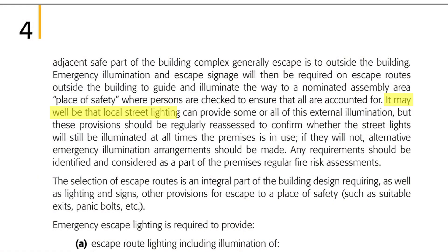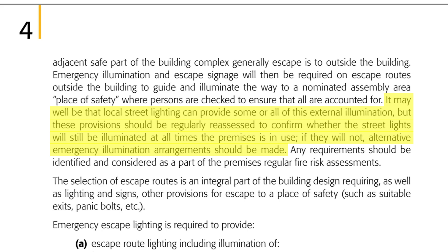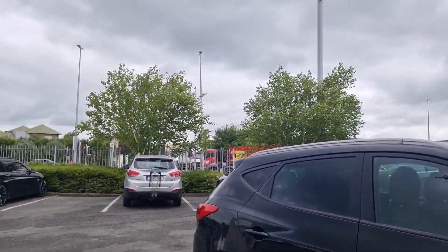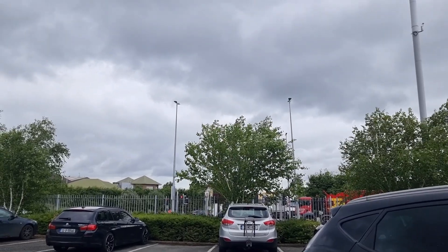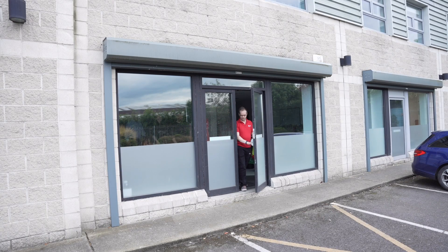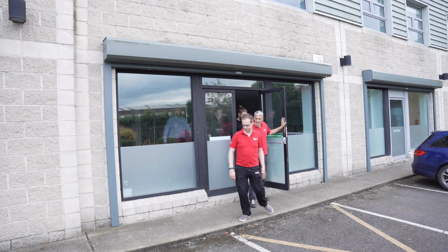Before worrying about providing emergency lighting along a path to the assembly point, the guide notes that local street lighting may provide some or all of this external illumination, but these provisions should be regularly reassessed to confirm the street lights will still be illuminated at all times the premises is in use — if not, alternative emergency illumination arrangements should be made. Also, the assembly point must not be an internal courtyard; outside means a place where people can get away from the building entirely.